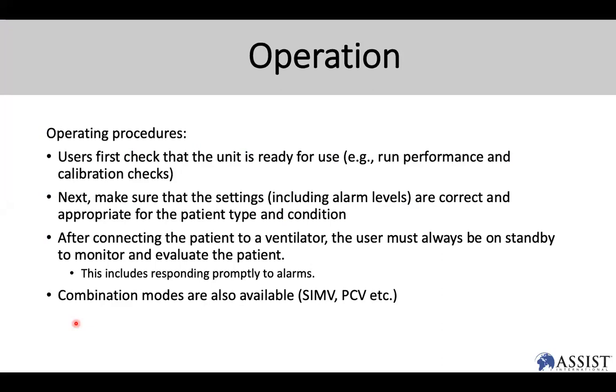And typically, when it comes to utilizing a ventilator, here are some basic things you have to keep in mind. You always have to conduct system checks to make sure the unit is ready. So we're talking about running a performance test, calibration checks. We want to make sure that the settings, including alarm levels, are correct and appropriate for the patient type and condition. And after connecting the patient to a ventilator, a user must always be on standby to monitor and evaluate the patient. If you are using an anesthesia machine as a ventilator, it is highly recommended that an anesthesia professional be available at all times next to that machine to make sure that it is operating as intended.